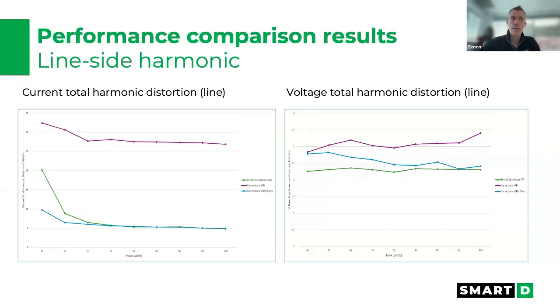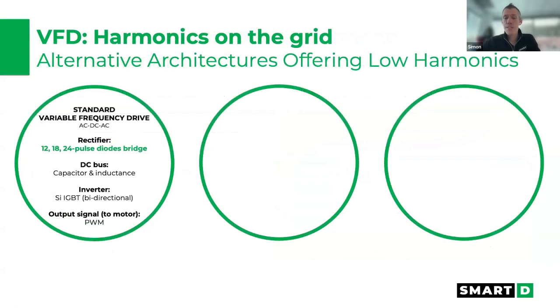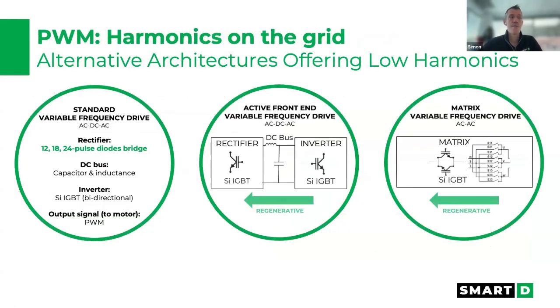Now you could ask me, okay, that's fine for a standard drive with external filters. What about these integrated low harmonics drives? In this case, you can have a multi-pulse drive. You can also have an active front end drive that integrates an active rectifier instead of the diode bridge. And you also have these matrix architectures, which are AC to AC.